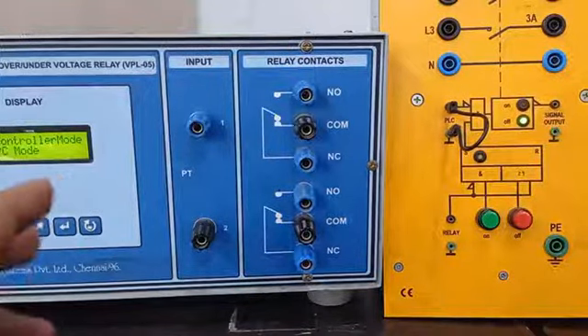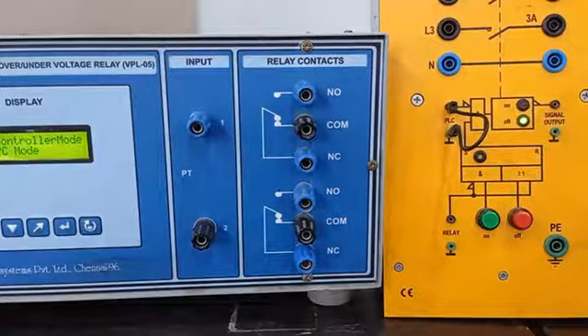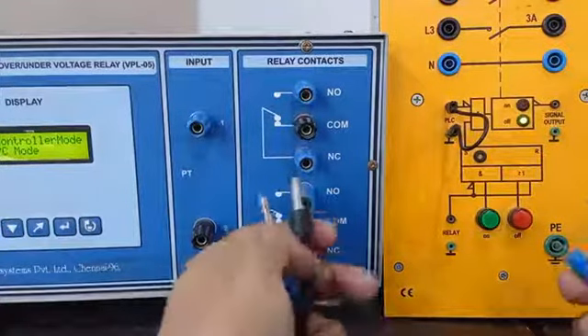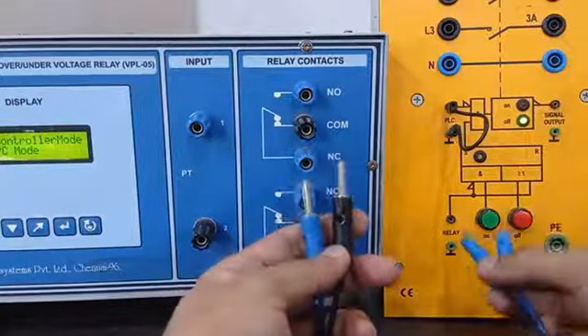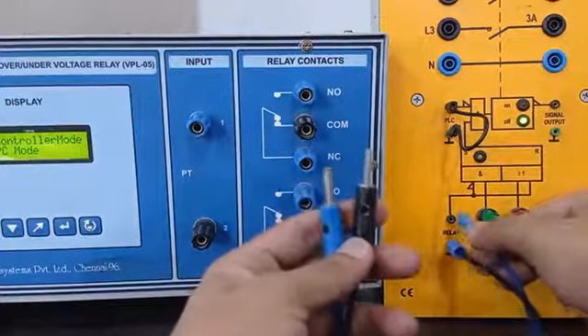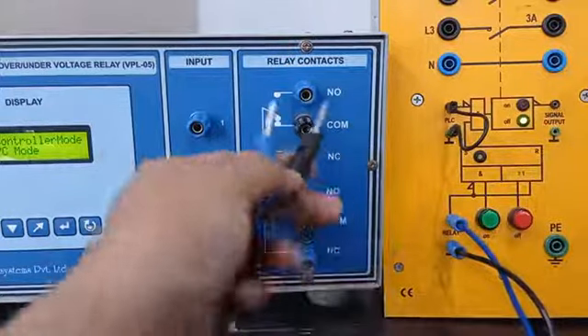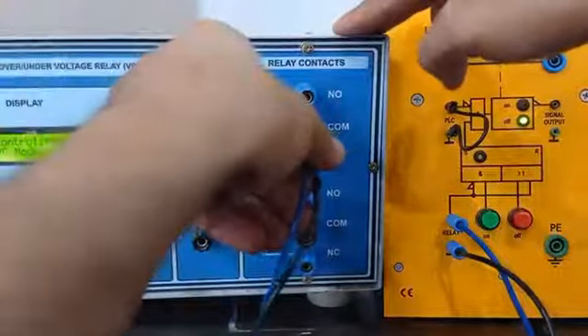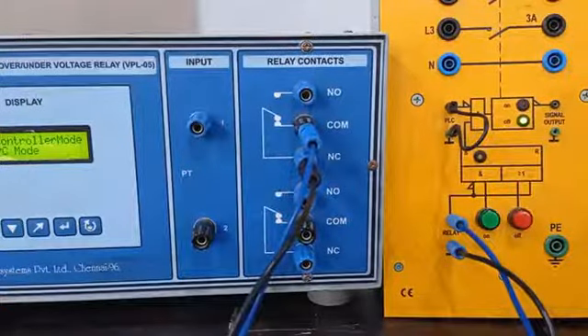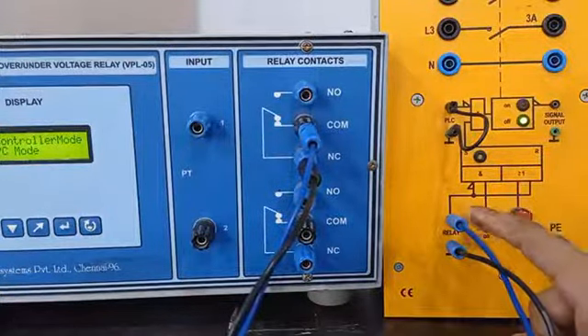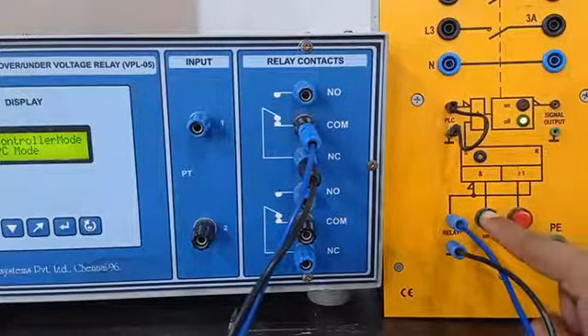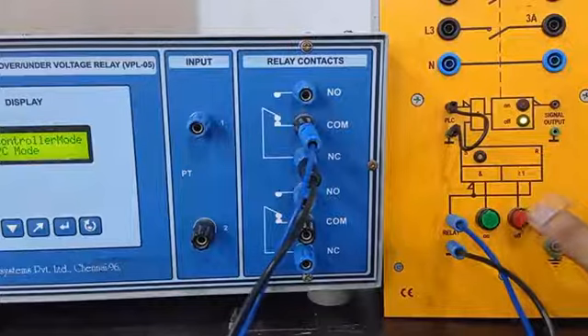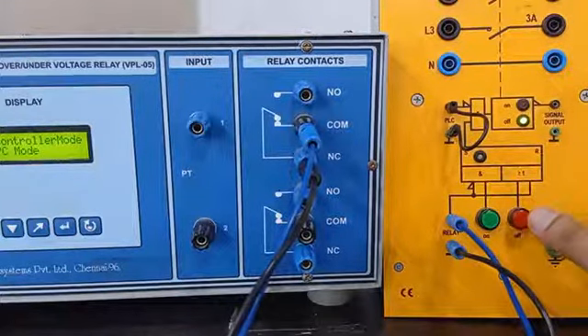Here, with the help of this relay, I will control the circuit breaker operation. In order to connect the circuit breaker relay terminal with the normally closed contact of the relay, I will insert these two terminals of this connecting wire over here. And with the help of this banana connector, I will make the connection with the normally closed contact. In normal condition, these two contacts are closed, so now it is short-circuited across the relay contacts. Now if I press the start and stop button, I can have manual operation of the circuit breaker. When the relay trips, it will also result in tripping of the circuit breaker.